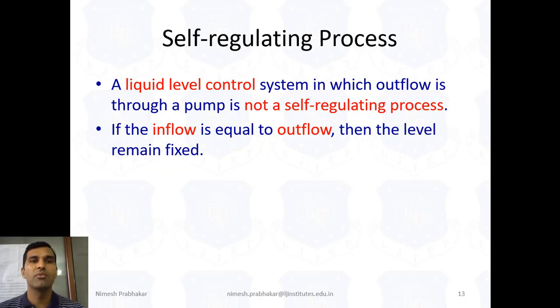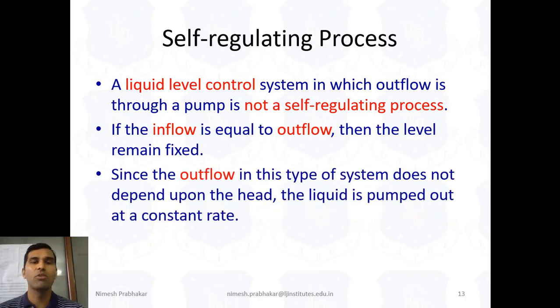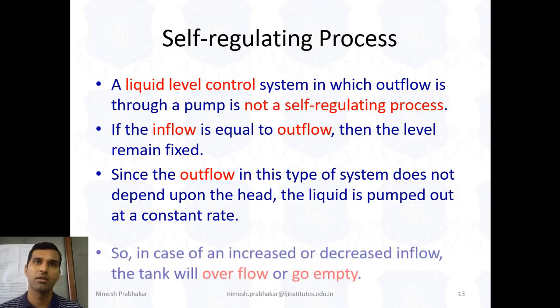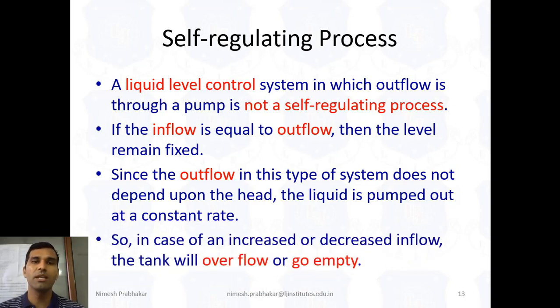If the inflow is equal to the outflow, then the level remains fixed. Since the outflow in this type of system does not depend upon the head, the liquid is pumped out at a constant rate. So in case of an increase or decrease in inflow, the tank will overflow or go empty. That's why we require one controller for controlling action. So this is not a self-regulating process.